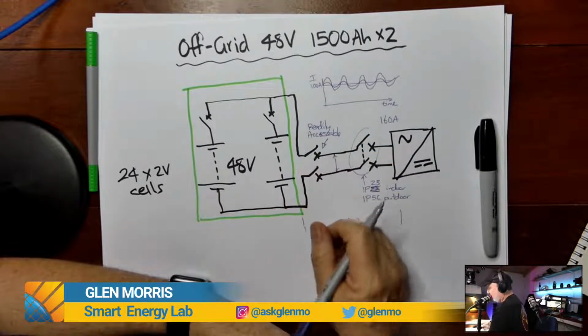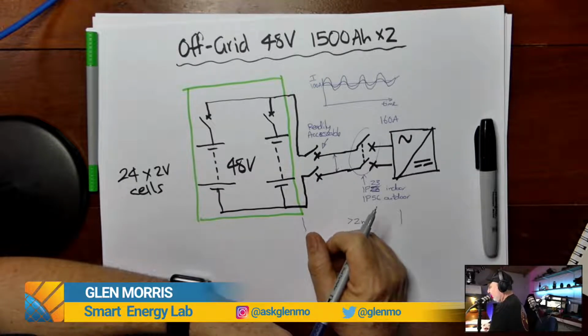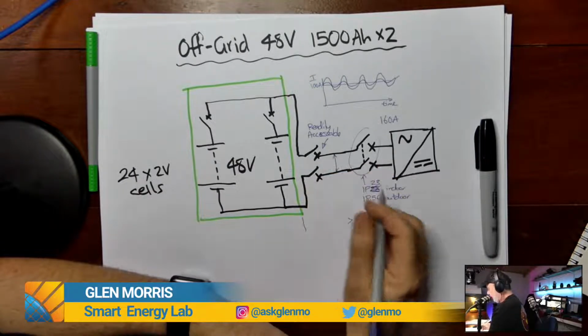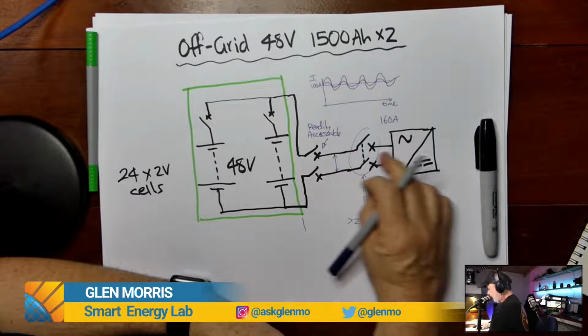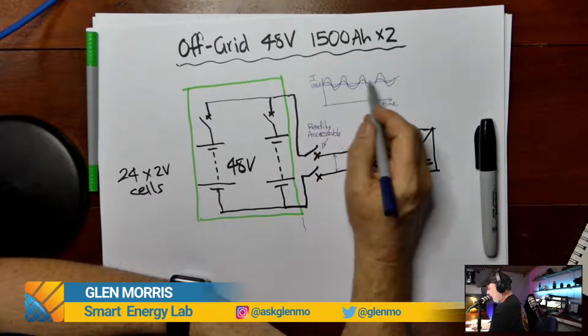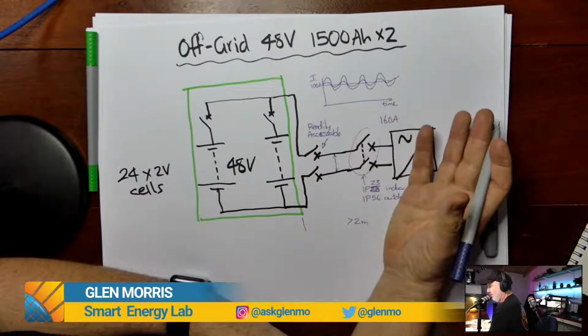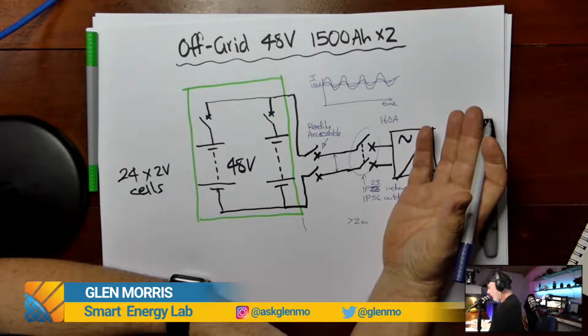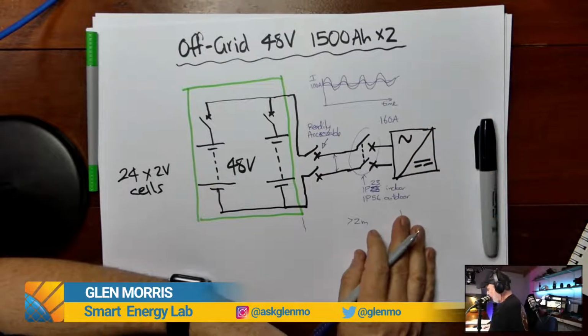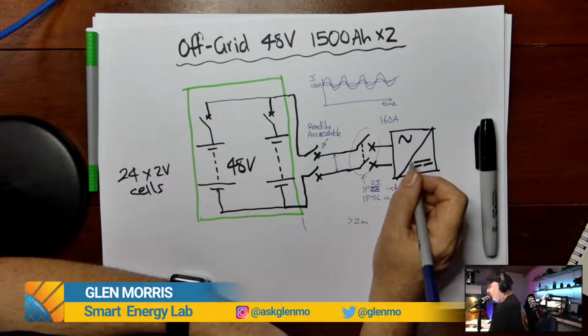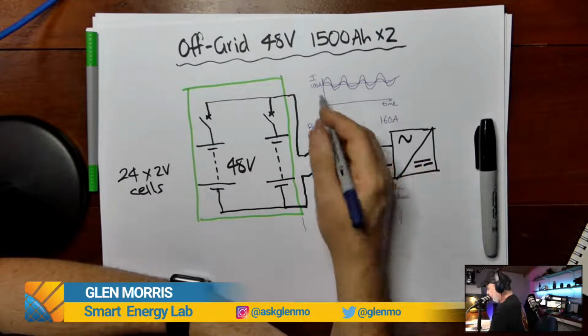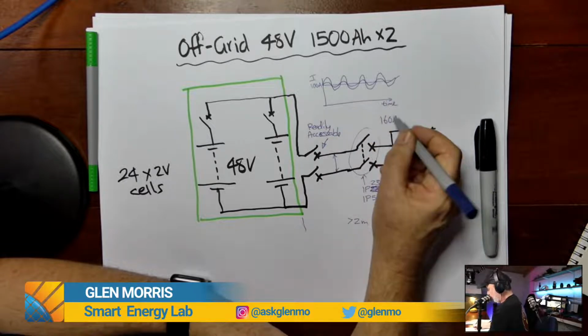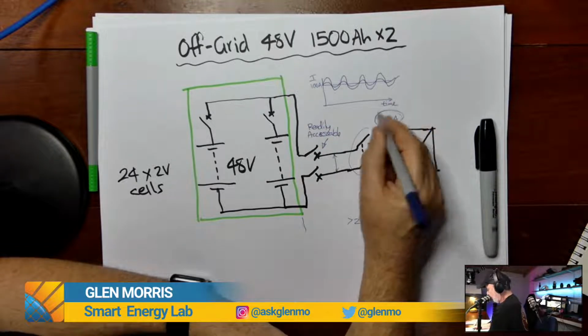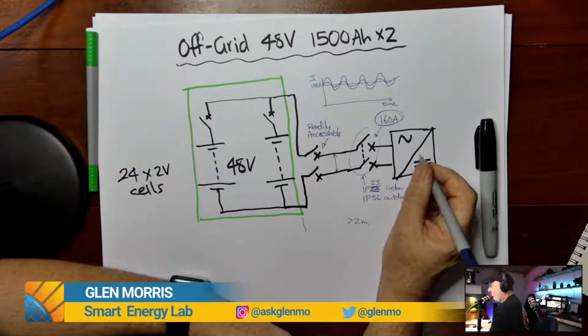So you should be running your DC cables as close together as you can, so as to reduce the loop area and therefore the inductance of those cables, and that'll help minimize this ripple current. So that's just good practice. It's not part of a requirement of the standards, it's just good practice. But you should check with the manufacturer of the inverter. They might give you some guidance on ripple current for their product, and that needs to be factored in when you consider the value of this circuit breaker here.